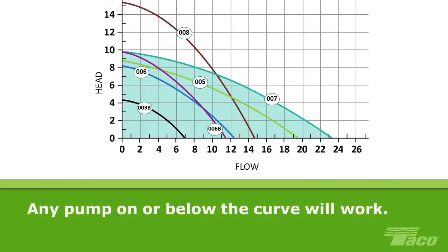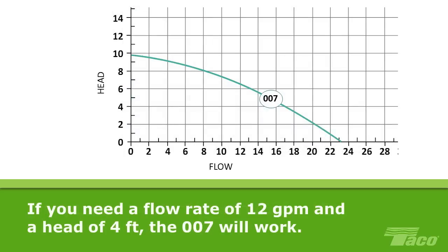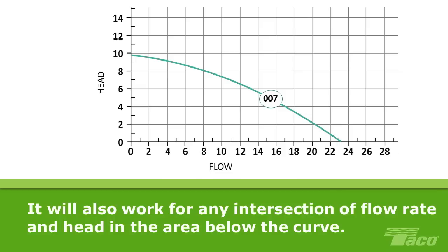Reading the pump curve makes it easy to choose a pump for a particular hydronic system. Technically, if the head and flow operating point of your system is located on or below a given pump's performance curve, then that pump will be sufficient to do the job. So if your system requires a flow rate of 12 gallons per minute and a head of 4 feet, the 007 will easily meet those requirements. It will also meet the system requirements if you need a flow rate of 6 GPM and a head of 2 feet, or 5 feet, or any other intersection of flow rate and head in the area below the curve.